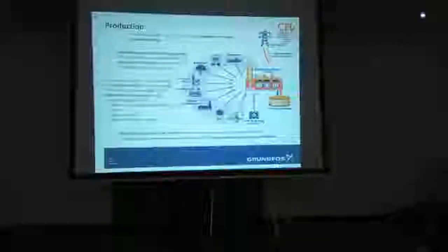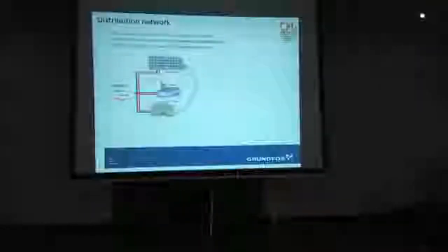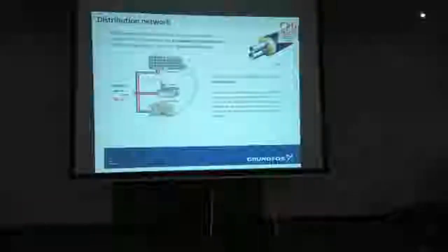Not just the network pipe, even though it might be 600 mil diameter. The distribution network is made from a series of insulated pipe. Sometimes single pipe insulated, sometimes double pipes. And there's obviously a network of people who sell this kind of equipment. And there are companies whose only job is to install that kind of stuff from A to B. They join the dots from here to here to here. So flow and return from the main centres into commercial properties, industrial and housing. Now, all of those could have different temperature requirements.